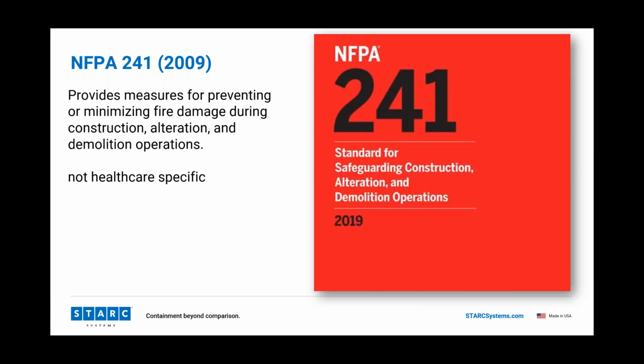So 241, what is it, right? So let's start there. What is 241 and why am I showing the 2009 edition? Well, we'll talk about that too. So 241 is our safeguard for protection against fires during construction, alterations, demolition, and its goal, its purpose is to prevent or minimize fire damage during those operations, right? One thing that's important to note is that it's not healthcare specific. It is adopted by some jurisdictions separately outside of NFPA 101. So you have to be cognizant and careful. Even if it's not adopted, it is a best practice.